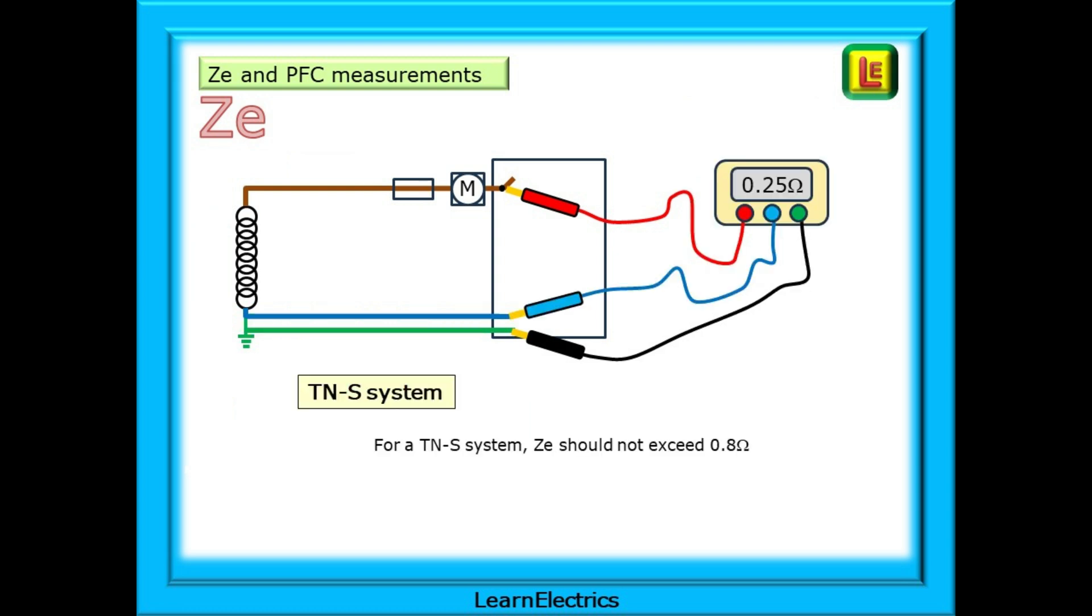With a TNS system the testing is exactly the same. Whether you use a two wire test or a three wire test is between you and your meter. For TNS systems we are looking for a ZE that does not exceed 0.8 ohms. The type of cable used in TNS systems is different to TNCS. It is older technology and has a slightly higher resistance reading.